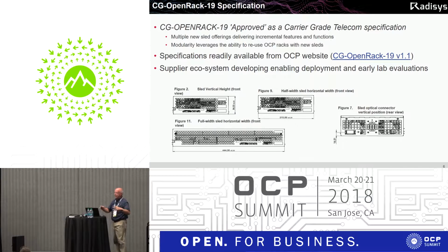The spec itself, of course, these are just some snippets out of the spec, but the spec defines the interface between a plug-in sled and a rack. So it doesn't tell you how to build a rack or what the rack has to do. It doesn't tell you what goes on specifically inside a sled, but it tells you how those two mate together. I think on the lower right, you can see the back of a sled. And so the power connection is the same power connection that's in Open Rack that we share. It's a 12-volt system, the same.